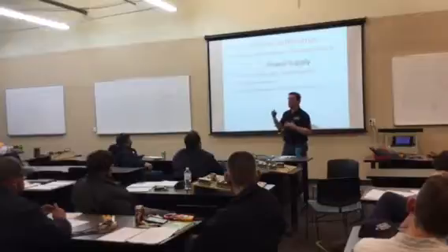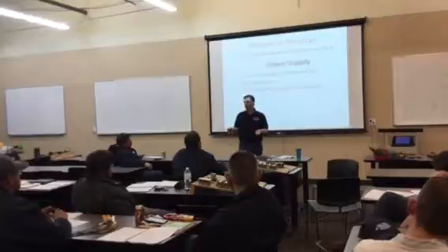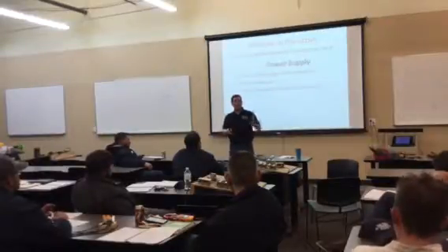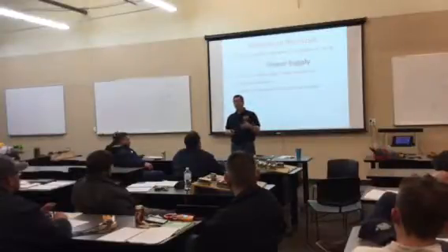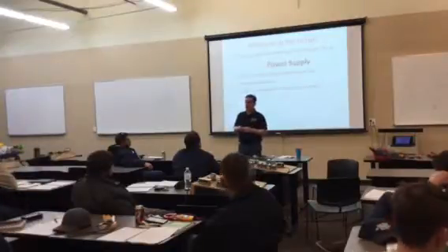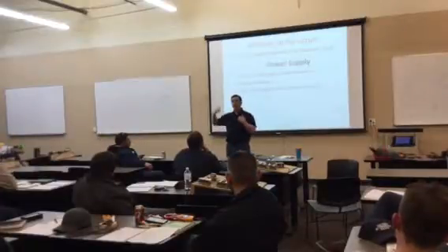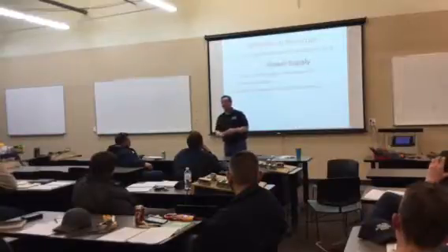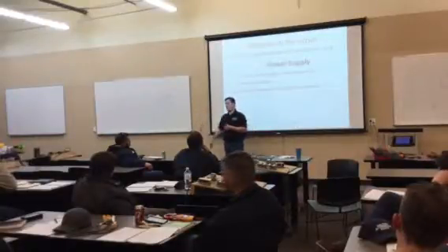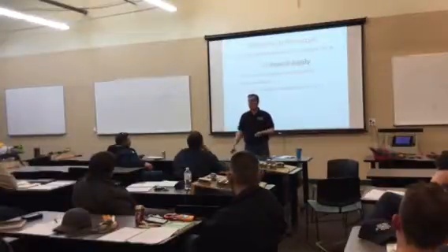In a lot of older homes, especially in Fort Collins and in Loveland, I was driving around, a lot of homes built in the 1950s, from the looks of the 40s and 50s. A lot of those homes originally had 60 amp service, is what it's called. The feeders feeding the house are capable of supplying 60 amps of current. The circuit breaker panel is capable of supplying 60 amps total of current. You add on air conditioning or add on a tankless water heater, you don't have enough power capacity in those existing lines to feed the new additional power requirement. Or if you're going to add a jacuzzi or something like that. Those are all good reasons to upgrade the panel to a physically larger power capacity.